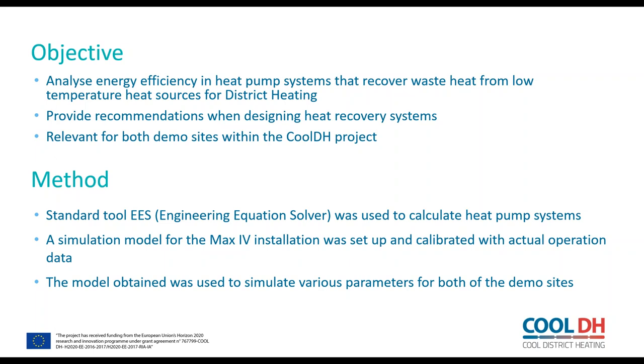So this was a theoretical study, but based on the actual operation that was installed at the Max 4 plant in Lund. So the tool EES, not to be mixed with the ESS, was used to calculate the performance of the heat pumps and used to make parameter studies varying different parameters for the heat pumps, both in Lund and in Høje-Taastrup.